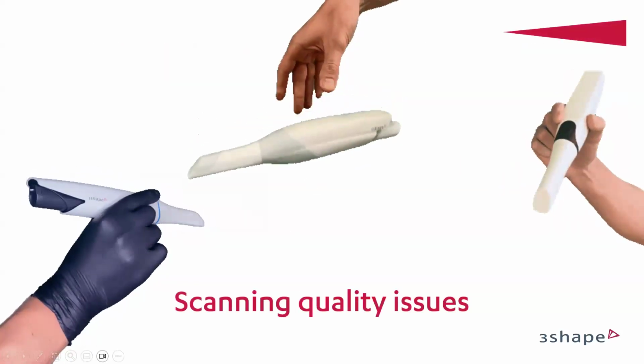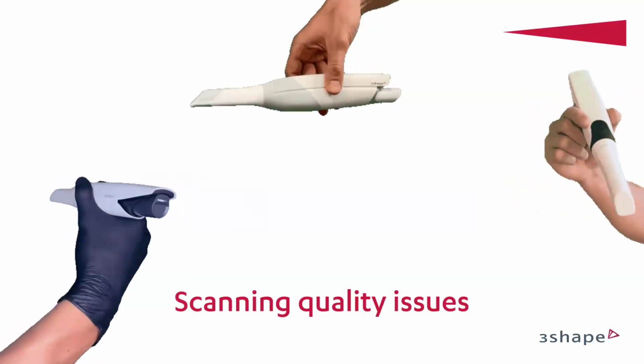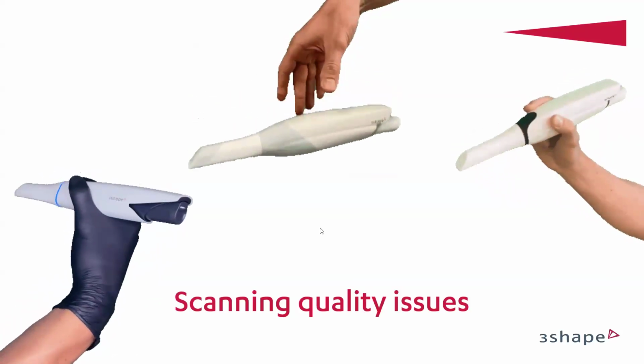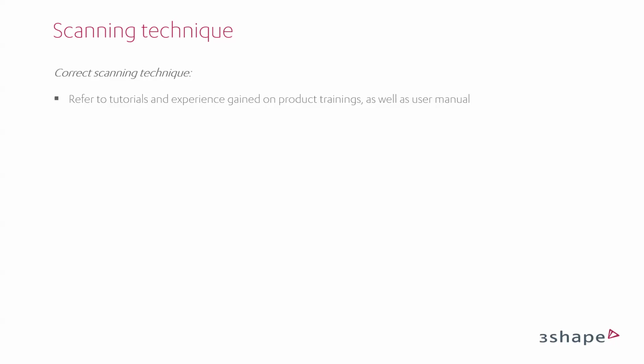Also, let's talk about some scanning quality issues that can be faced by our customers. The most important thing that affects scanning quality is the scanning technique. If we need to apply a correct scanning technique, we need to refer to tutorials and experience gained in product trainings as well as the user's manual. Another thing, we need to ensure that there is no strong external light interfering, affecting the scanning.